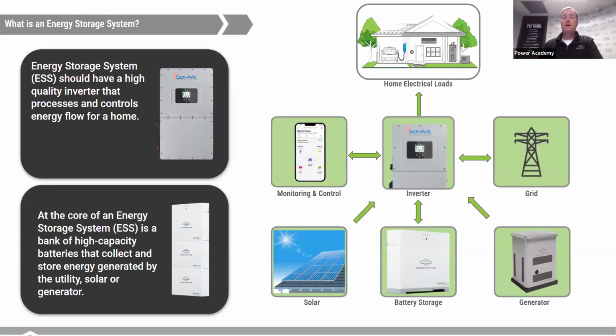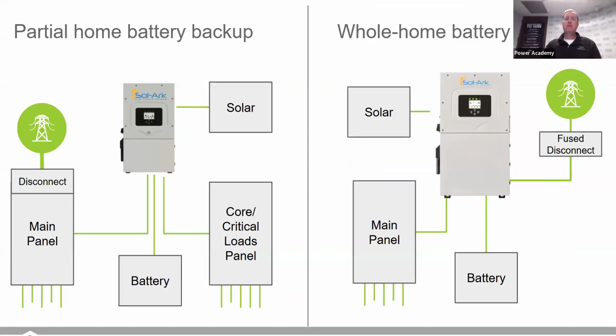Another thing I really like about Sol-Ark is their ability to pull in generators. With the automatic two-wire start signal, we can start a generator based on the battery's state of charge, charge the battery while also supplying home loads, run the generator at its most fuel-efficient point, save on run hours that would require more maintenance, and—most importantly, I think—save on the noise associated with those generators.